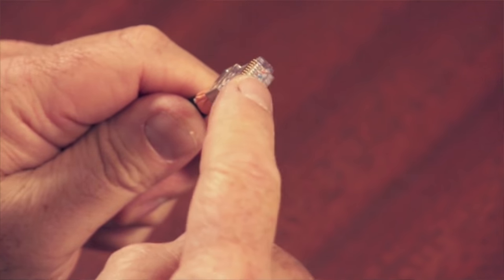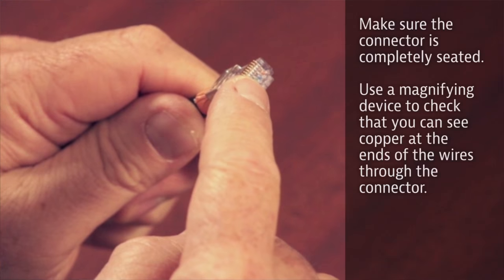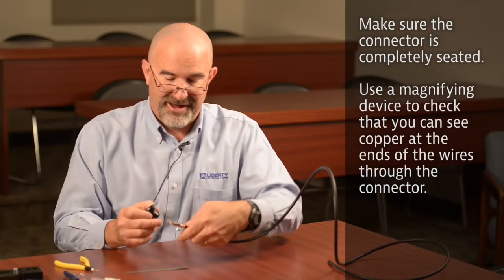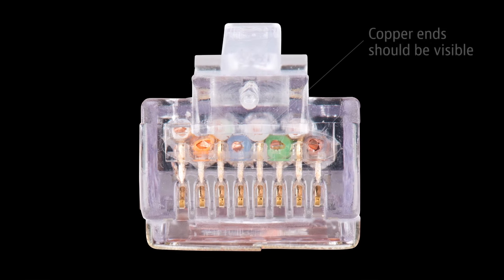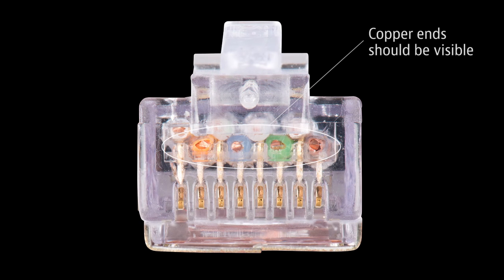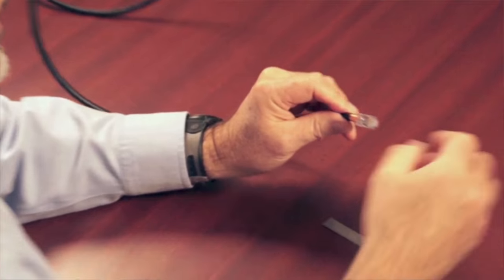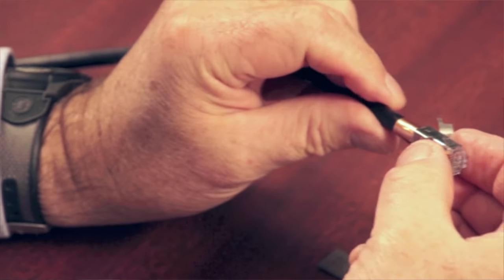The way you tell whether your connector is seated all the way is if you can see copper at the front of the connector. I'm going to validate mine with a 5-power jeweler's loupe. Validate your color code and whether you have copper showing, which I do. Now I'm going to slide the strain relief up and bend it over by finger power.